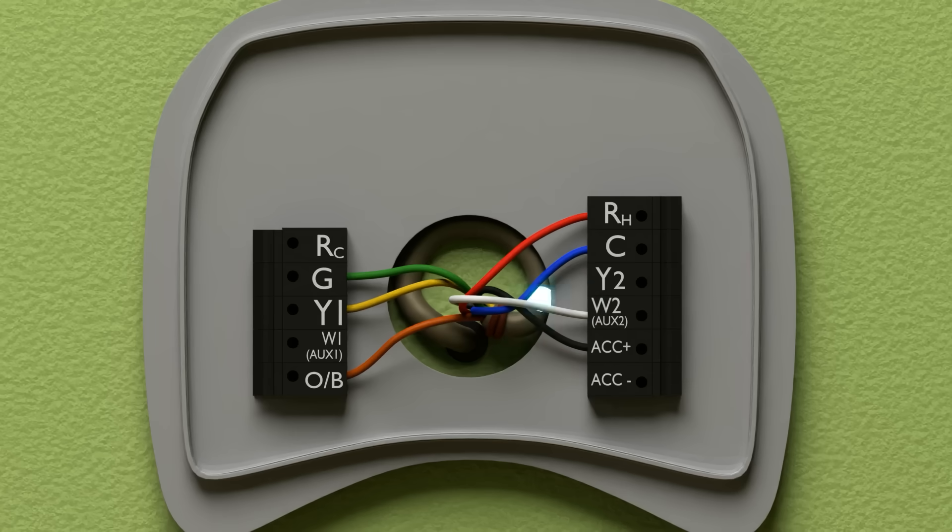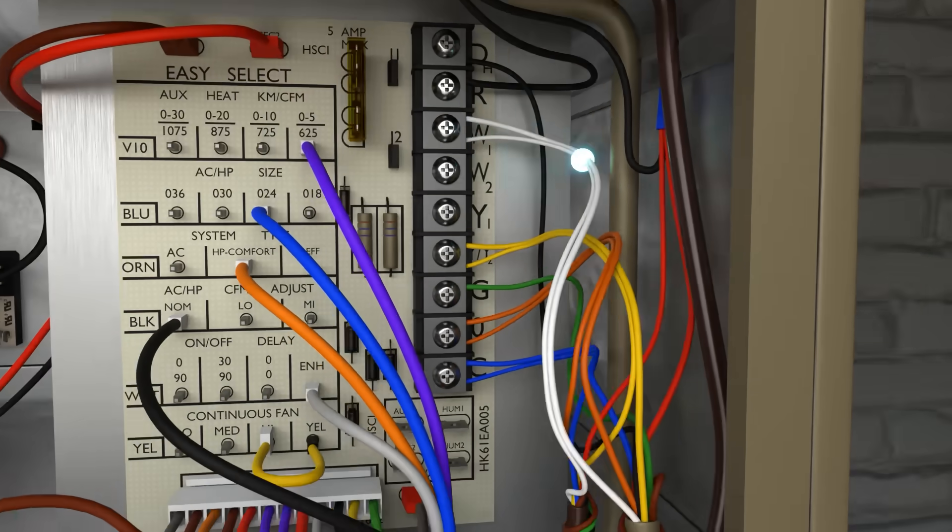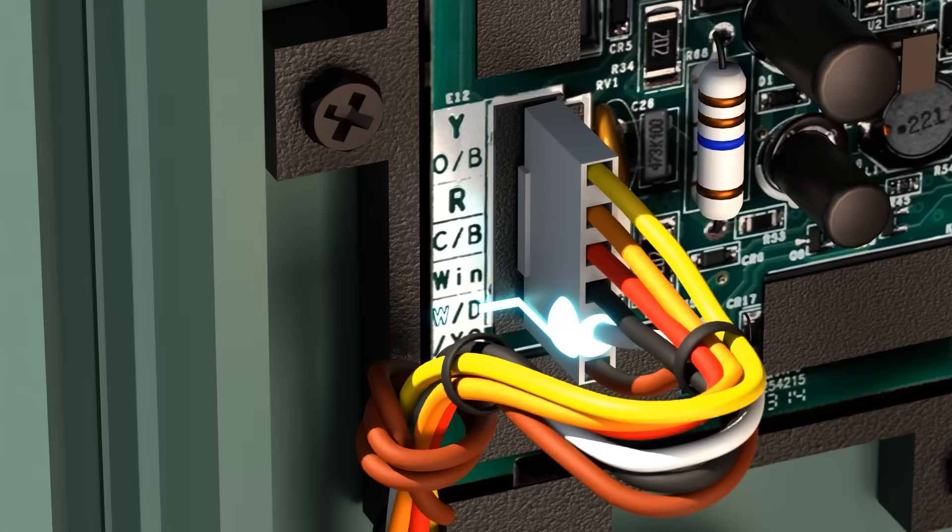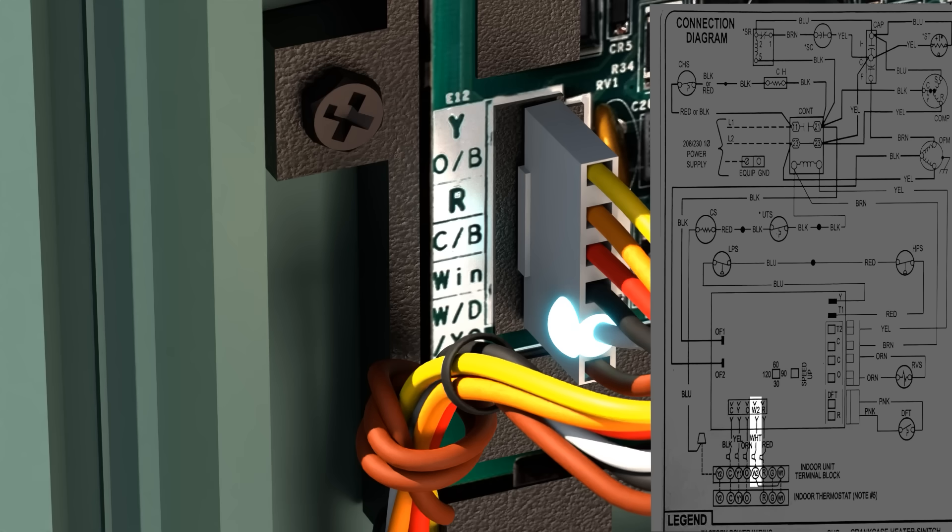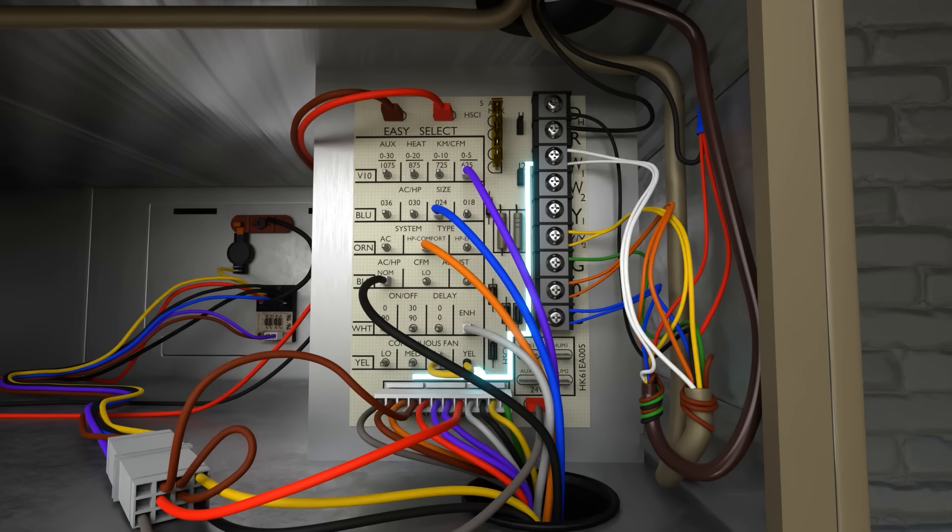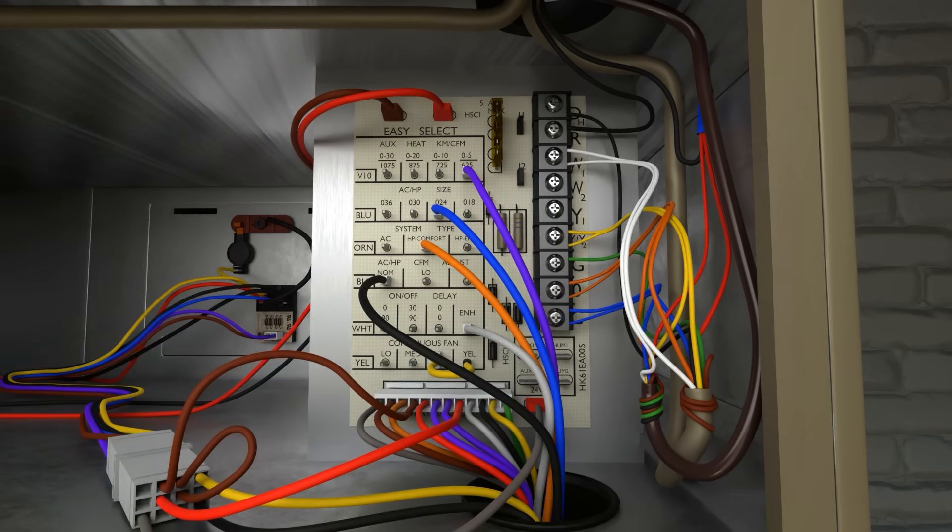Next, we show our auxiliary heat, which is white or W2. Once again, this wire connects to our terminal block on the heat strips and then goes outside and connects to W on our defrost board. This allows the defrost board to backfeed and bring on electric heat as well as the thermostat. So either the thermostat or the defrost board on the outside has the capability of bringing on the electric heat.